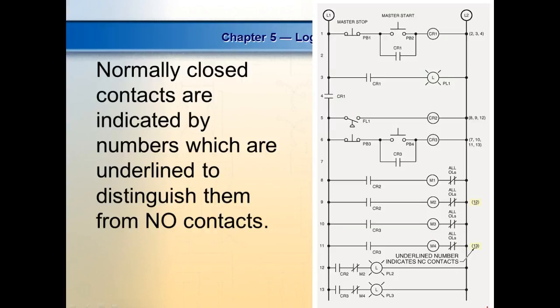What we're trying to do is see what controls the motor. We call this a control diagram, or a line diagram. A control relay's contacts are only used within the line diagram - they never leave, never will be in a power diagram. Normally we have two different drawings: a control diagram, and a power diagram.